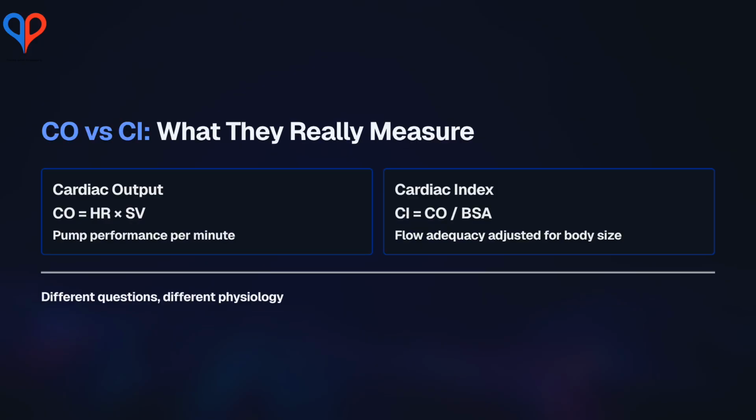Thermodilution cardiac output is computed from the temperature time curve after a cold bolus travels through the right heart. This method assumes stable, laminar forward flow. Severe tricuspid regurgitation violates that assumption by causing regurgitant washout, yielding a falsely low output. Intracardiac shunts divert the injectate unpredictably, making the curve unreliable. Extremely low cardiac output prolongs transit time and destabilizes the measurement.